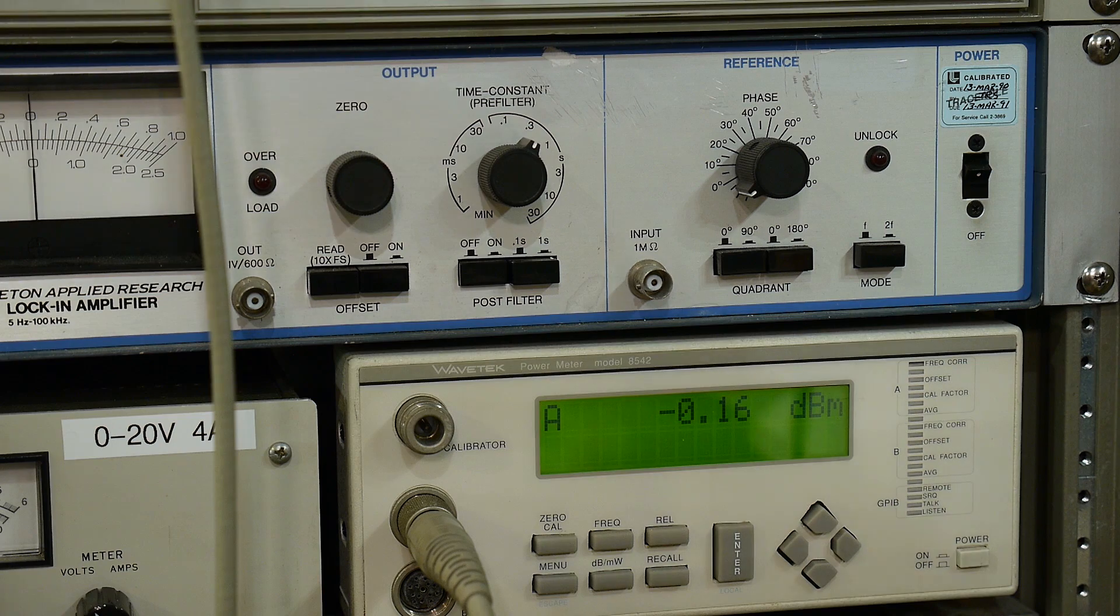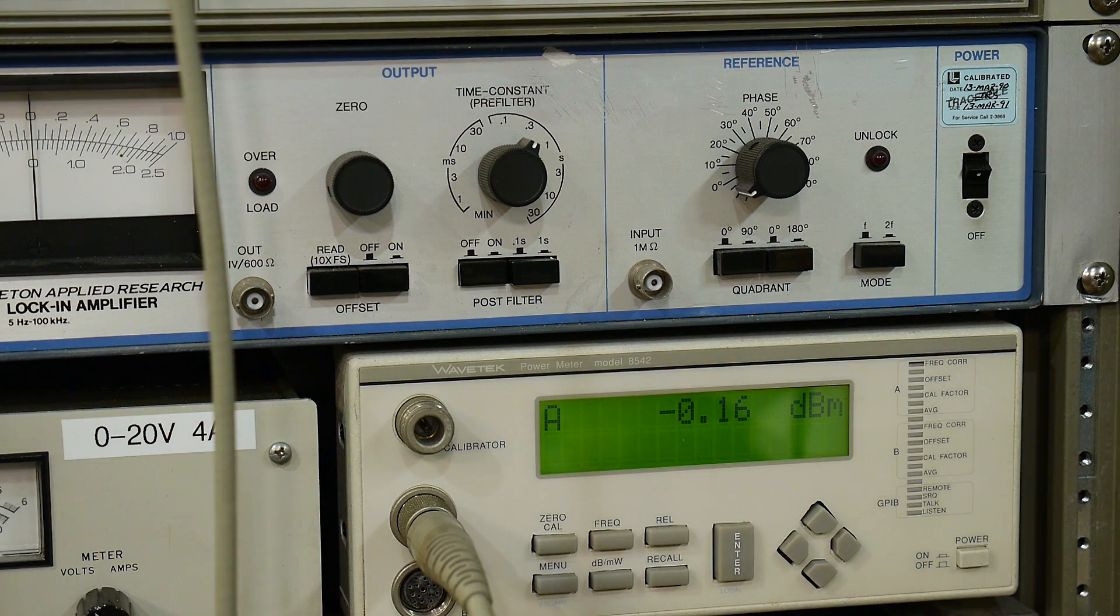That is very, very close. Let's see if we can tweak it and make it exactly 0 dBm. I mean, that's pretty close. That's probably all you really need, but since we can do it, let's see if we can't tweak it. So I need to be able to see what I'm doing here. It's going up, I think. There we go. That's going down. Oh, there we go. There we go. 0 dBm.